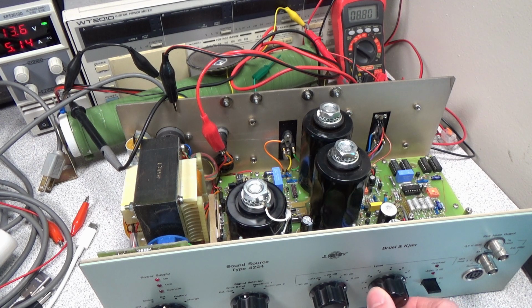So the failure point on this unit appeared to be a diode, but the actual failure point you couldn't see was a capacitor. The diode just had less thermal mass, so when the capacitor failed, it didn't blow up - instead the diode, which doesn't have much thermal mass, was the thing in overload condition because it was trying to drive that dead short capacitor. It's the thing that went pop.